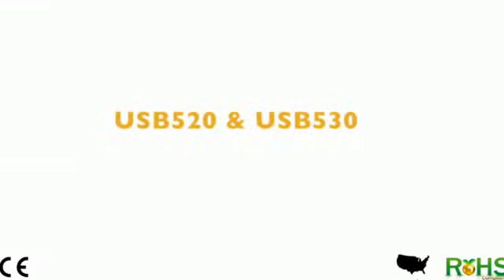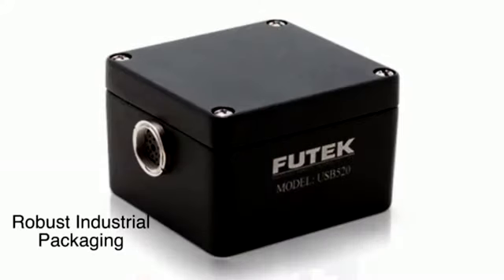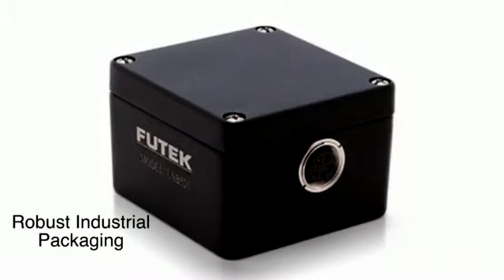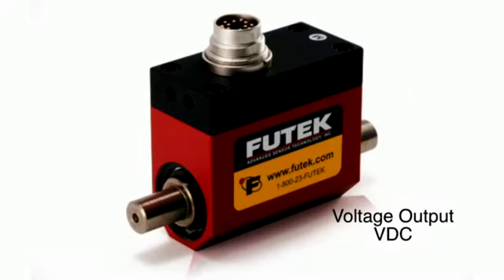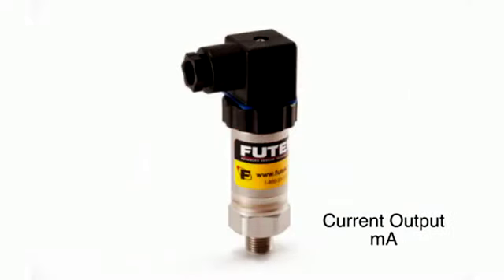Hi, I'm John with the FUTEK Technical Support Team, and in this video I will be introducing the USB 520 and USB 530 and going over their specifications. The USB 520 and 530 are one of our latest offerings in our very popular USB solutions family. Our goal was to create a single USB solution that can work with a large range of sensor output types. As a result, we engineered a high precision instrument that can work with millivolt per volt output sensors as well as with amplified voltage and current output sensors.